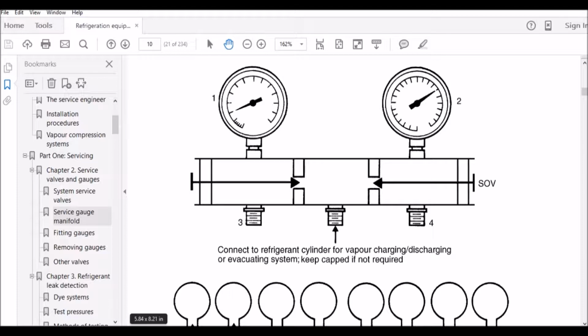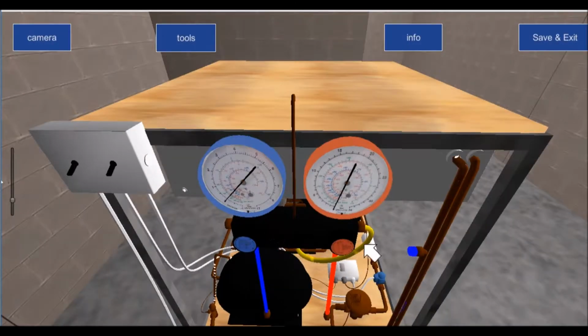So how I demonstrate that to you is I simply go here, and again, I explained to you about the Schrader, but I'm simply just going to connect the Schrader. So straight away, all I've done was take this hose and connect it to the Schrader fitting on the low side of the system. I disconnected, that'll go back to 0 in the real world. That's a bug for Shane to sort out. And I connect it again, it goes back up to pressure.